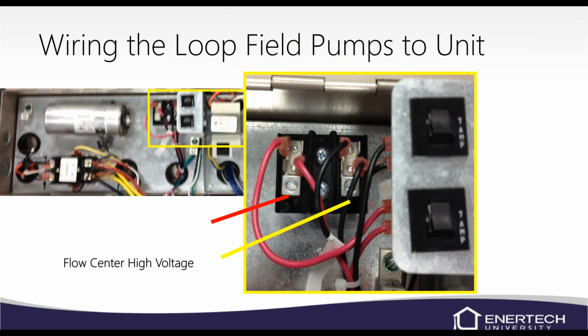Wiring loop field, I know this picture is kind of fuzzy there, but don't hook the flow center pumps directly to the contactor. We see that quite a bit, mainly because those guys don't see this little pump block that's back behind those 7-amp fuses. Those 7-amp fuses are resettable unless you trip them too often, and then they will stick open. You have to replace it. But the pumps are protected by those 7-amp fuses.